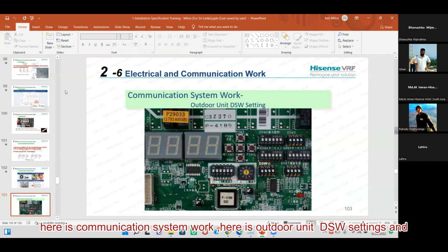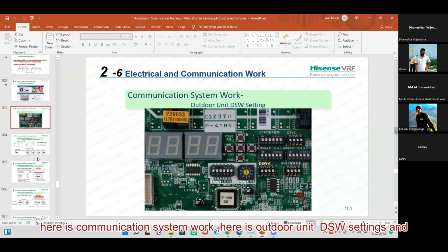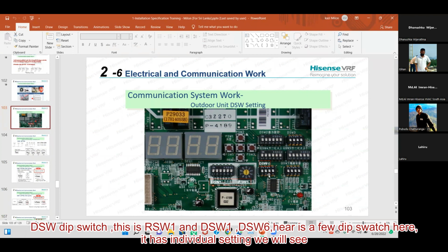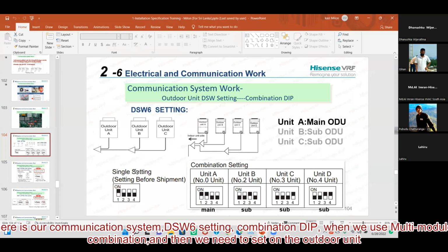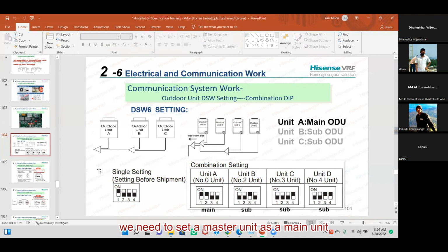Here is the communication system work. How do you need DSW setting? DSW is DIP switch settings, and this is the RSW1 and DSW1, DSW6. Here are a few DIP switches, each with individual settings. We will see. Here our communication system DSW settings. When we use multiple combinations, then we need to set the outdoor units. We need to set a master unit.